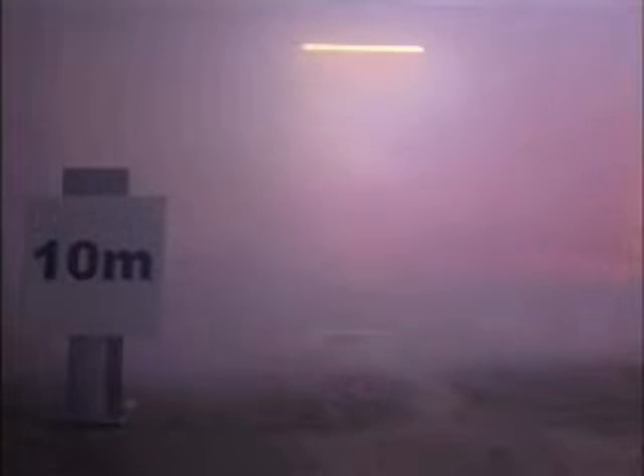For each test, the car park was filled with warm smoke, using smoke generators and warm air heaters for a period of 4 minutes, at which time visibility was reduced to around 10 metres. Once the car park was filled with smoke, the smoke generators and heaters were switched off and a selected ventilation system switched on and left to run until the car park was clear of smoke.